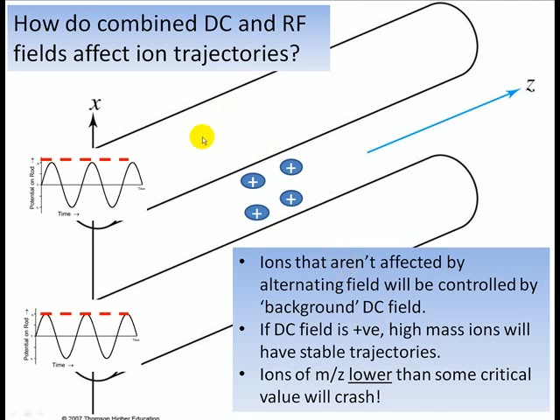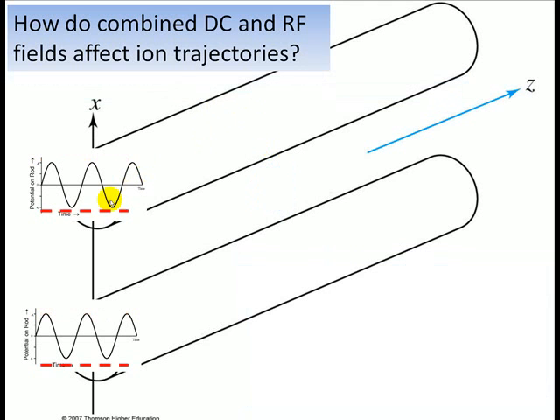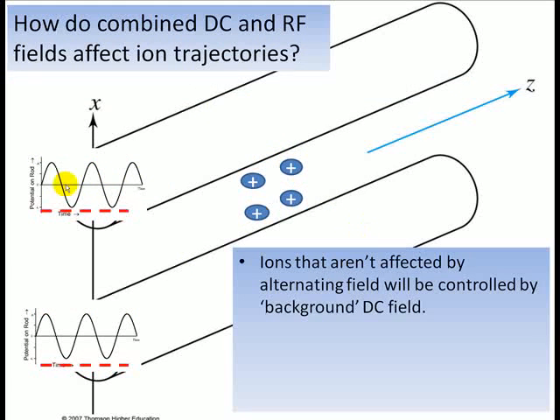So anyway, now let's look at the situation where the rods have a negative DC voltage. When the rods have this negative DC voltage, that tends to destabilize the trajectories. The ions would crash if they were not affected sufficiently by the alternating voltage. So in this situation, the alternating voltage has the chance to save them from crashing.